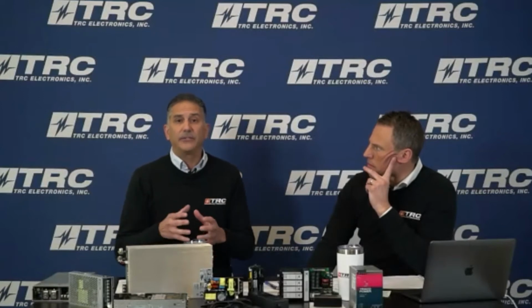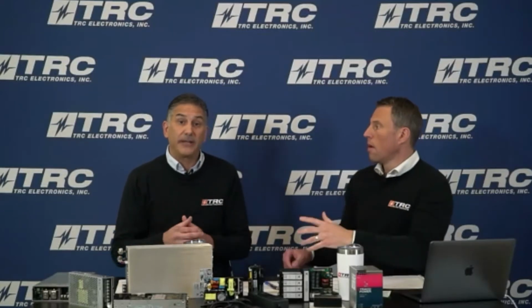While we're on the topic of AC inputs, we had a webinar last year about the top 5 mistakes, and one that's overlooked sometimes is the derating of the AC input. Most power supplies operate down to 85 volts, but there's a catch: at 85 volts there's more input current going into the power supply, which could overheat the internal portion of that circuit. So most manufacturers will derate that power supply by 10 or 20%, or ask the system designer to make sure they're not operating at full power at that level.